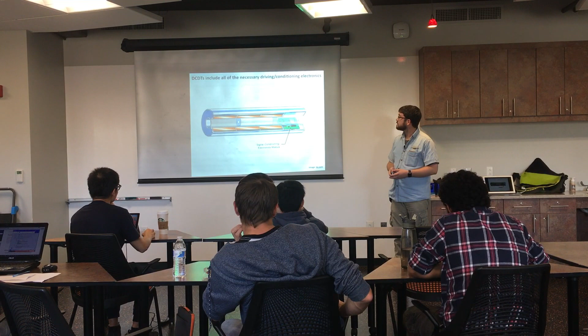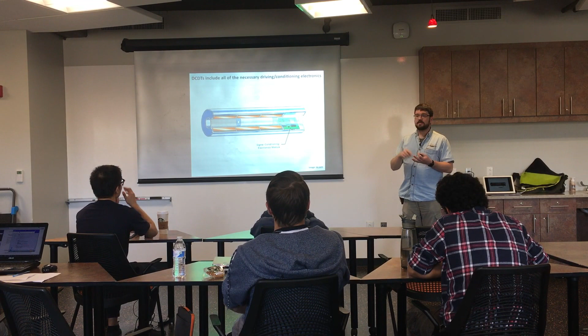This is what that looks like if you cut into one of them. You've got the windings down here, and generally on the back end of the transducer there's a small PCB with a microcontroller that generates the high frequency we drive it with, and that takes the phase and magnitude of the output to create a DC voltage.